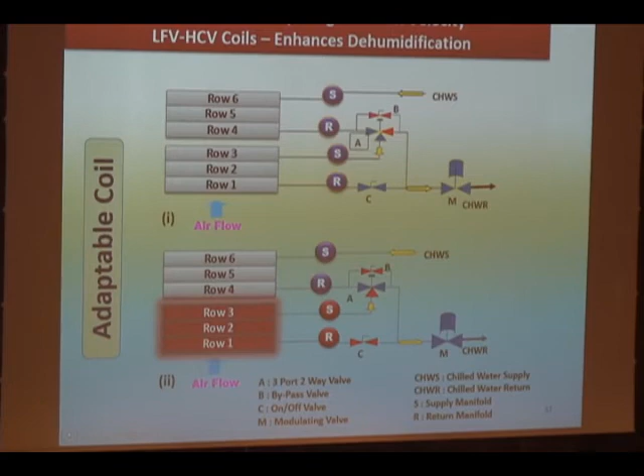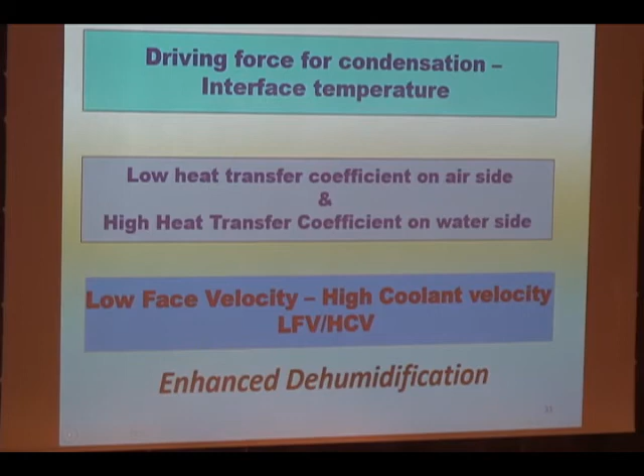And these are some of the requirements that I just mentioned. The combination of low air velocity and high water velocity keeps that surface temperature as cold as possible at all times. If the surface is cold, you pull out the moisture a lot more. The condensation is enhanced. You get enhanced dehumidification. So this is basically what the adaptable coil is all about. Let me move on to another technology or strategy that helps us in this process, heat pipes. Some of you may be familiar with it.